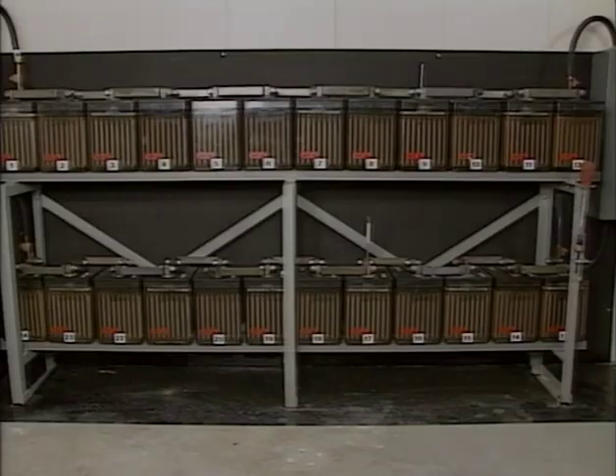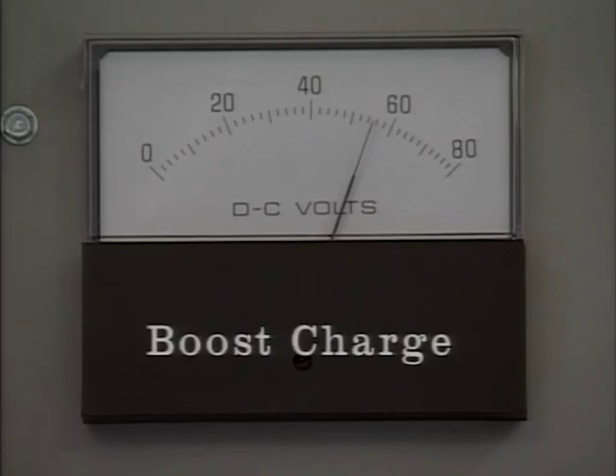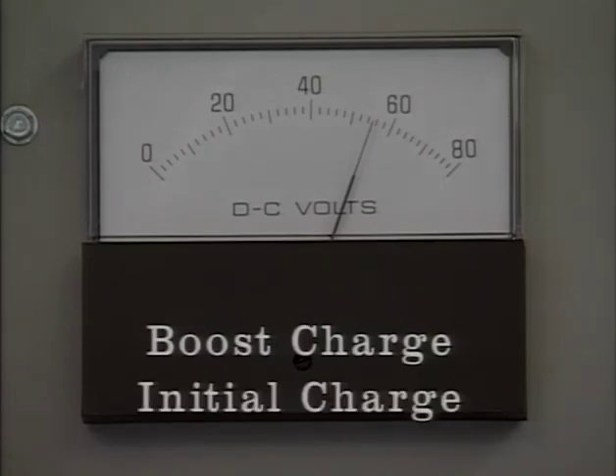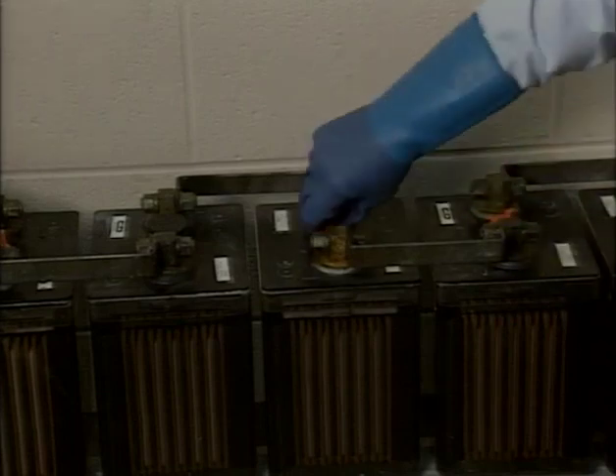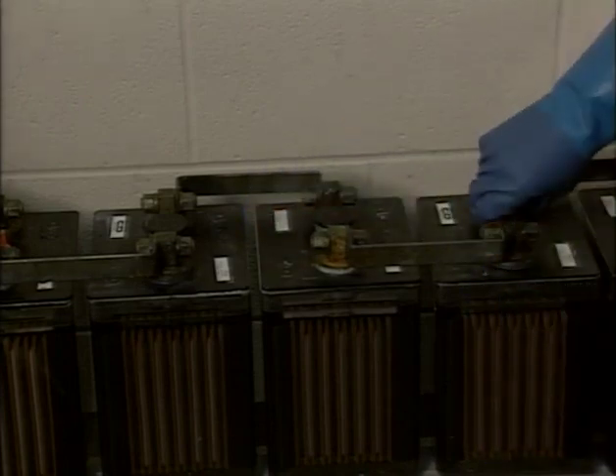As the cells discharge, sulfation occurs. The resulting sulfate crystals can be difficult to remove with normal charging and can prevent the cells from taking a full charge. For this reason, a freshening charge — a higher-than-normal charge voltage — is typically applied to wet-charged cells before they're put into service to ensure that the crystals are driven off the plates and the cells are fully recharged. A freshening charge is also sometimes referred to as a boost charge or an initial charge. Before it is applied, the cells must be properly installed and the shipping vent plugs are typically replaced with flame arresters.